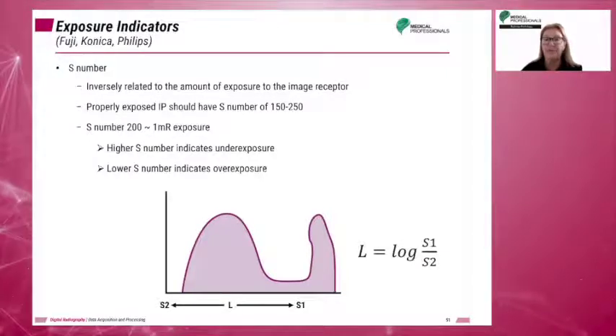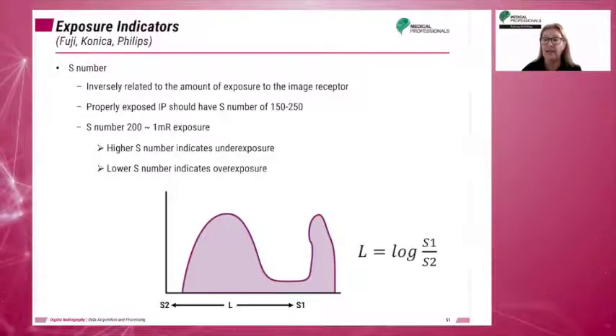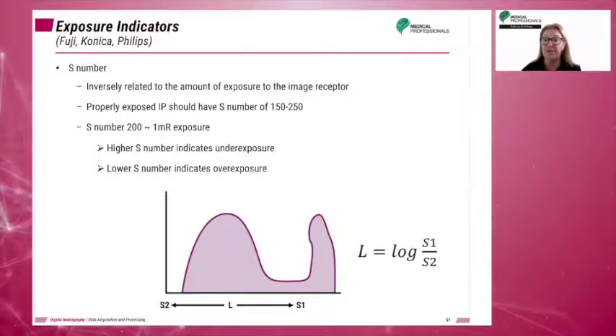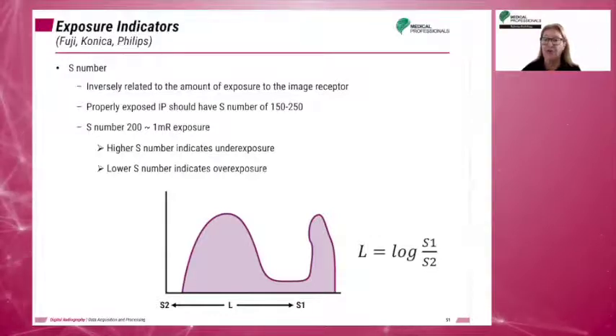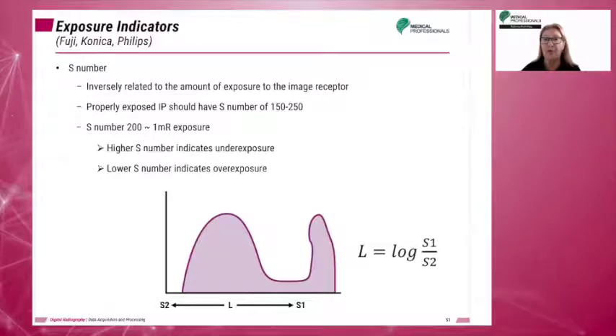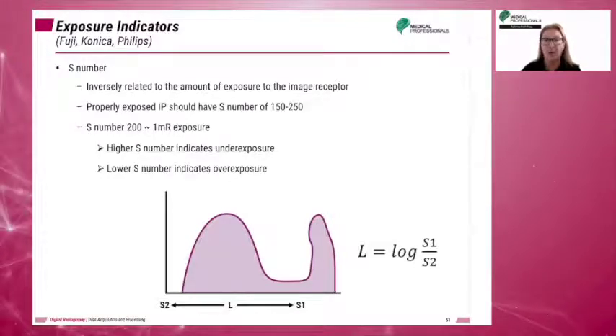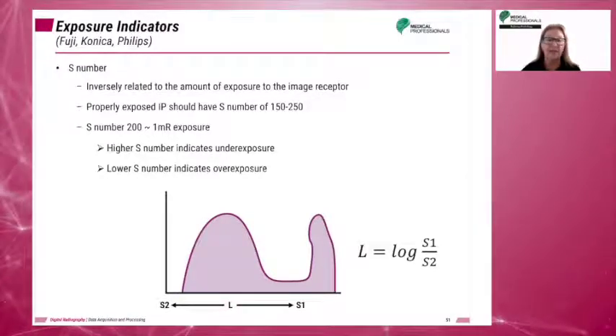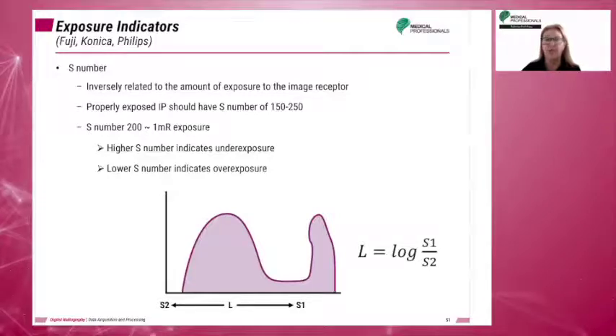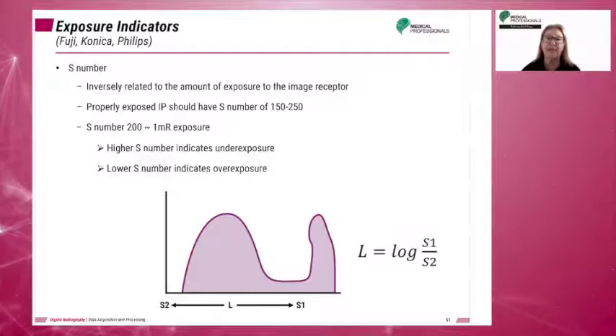With Fuji, Konica, and Philips systems, increased or high exposure to the plate leads to lower S numbers, and low exposure to the imaging plate leads to higher S numbers. Doubling the exposure reduces the S-value by one-half.